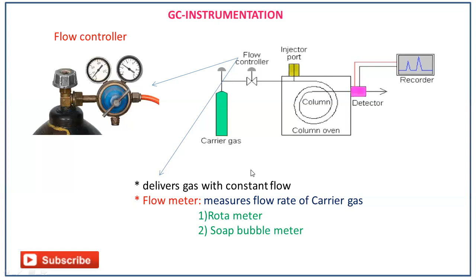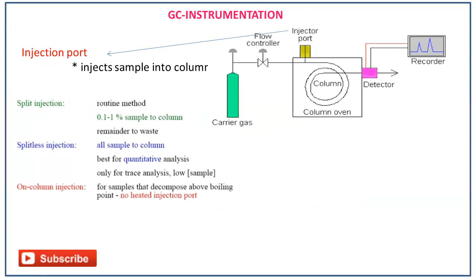And the next one is called the injection port, which injects the sample into the column. The injection port is present just above the column, at the head of the column. Here the sample gets injected, and we can have different modes of sample injection. The sample can be injected using three different modes: split mode, splitless mode, and on-column injection mode. But mostly we are using split mode.